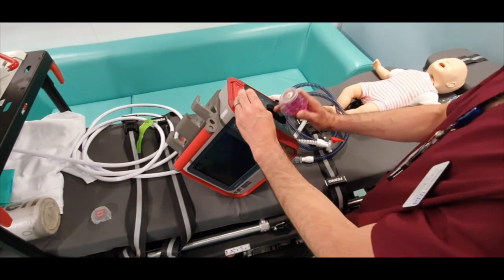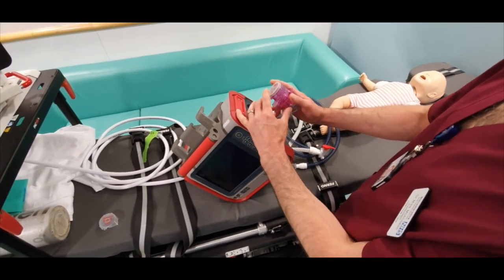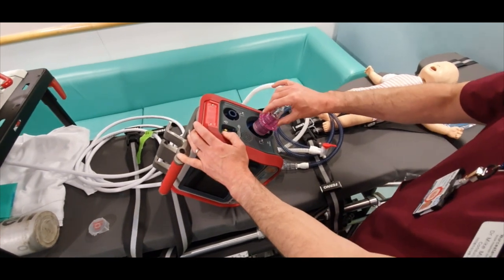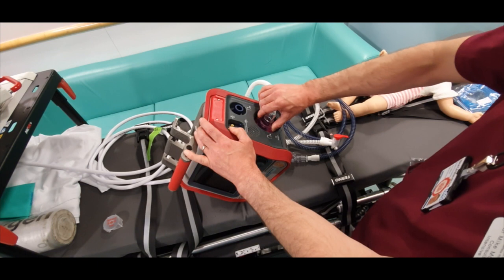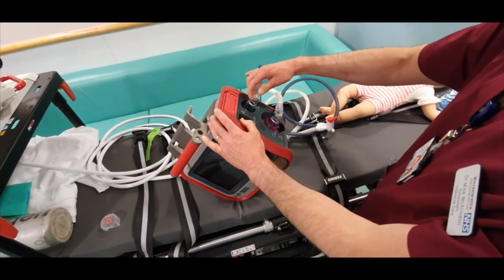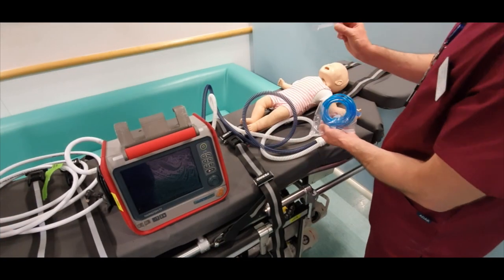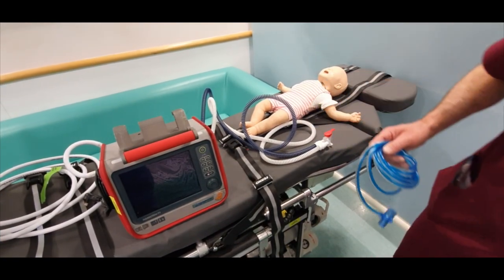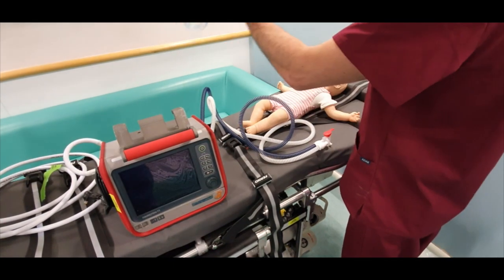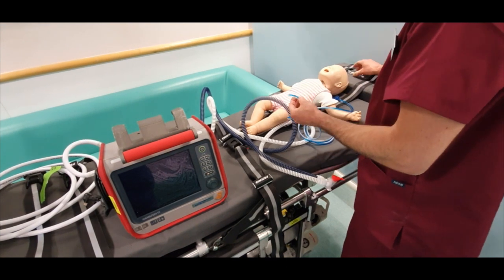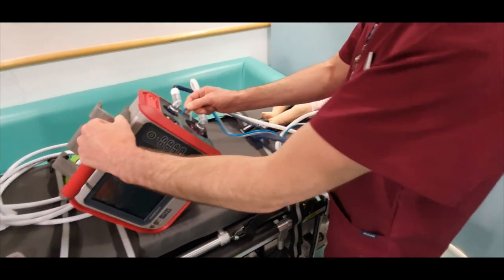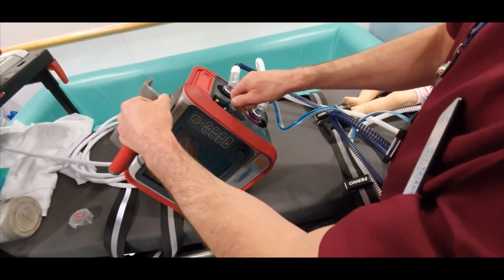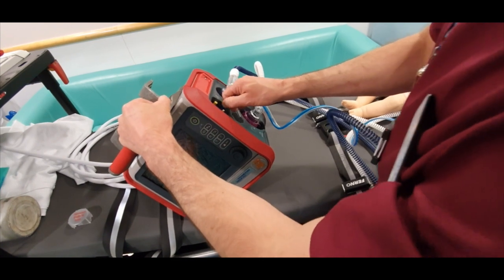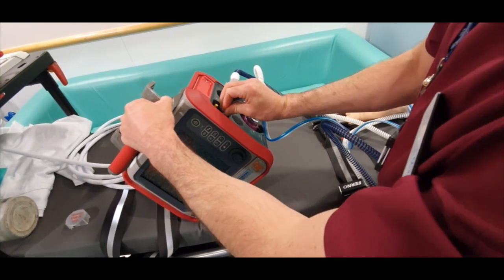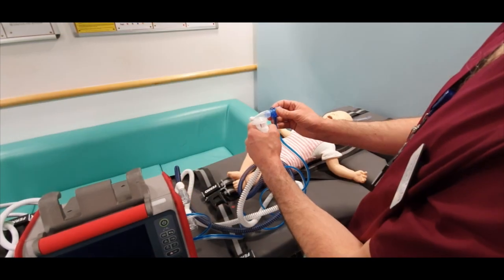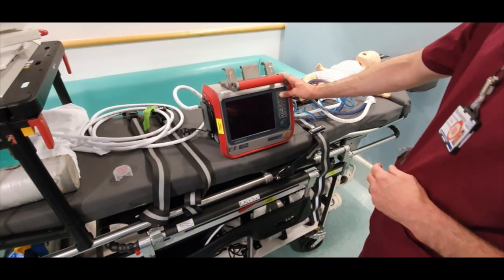Make sure the diaphragm is well seated and rotate the expiratory valve onto the ventilator outlet until it clicks into position. The inspiratory limb just pushes into position. The pressure and flow monitoring tubing is colour-coded, pushing onto the colour-matched nipples on the machine. Finally, the tubes are attached to the patient end before adding a paediatric HME and CO2 sensor.